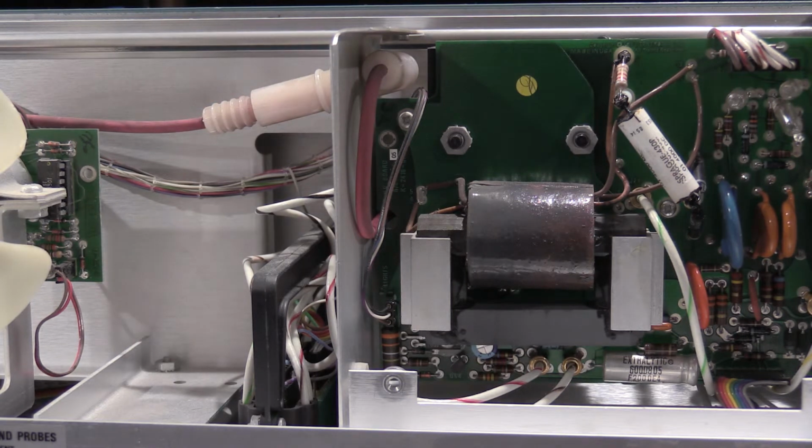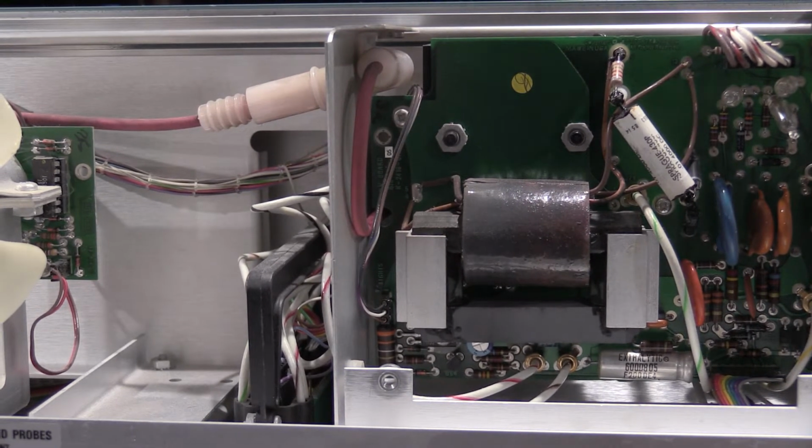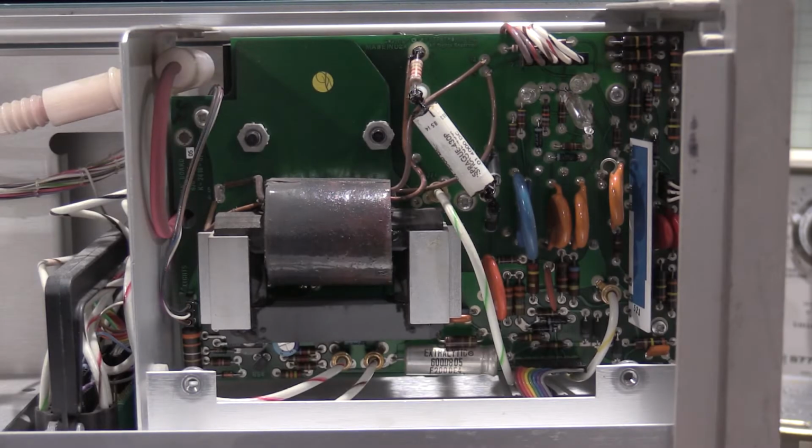So definitely not something, we're not talking about an inconsequential amount of voltage at the moment. This is 21 kV. And when you get into voltages up there, insulators start breaking down, things start getting jumpy. If you're following along, you're doing so at your own risk. So let me get the cover put back on, and we'll continue with the calibration.